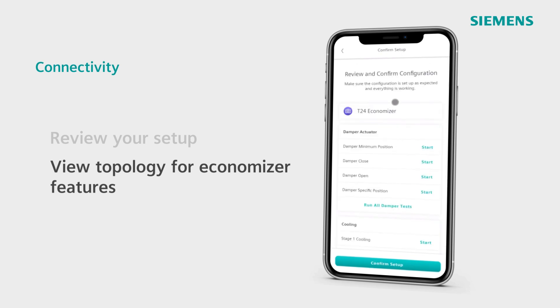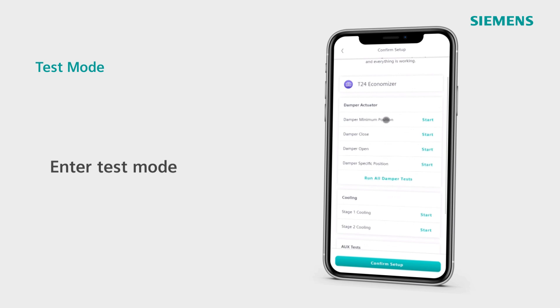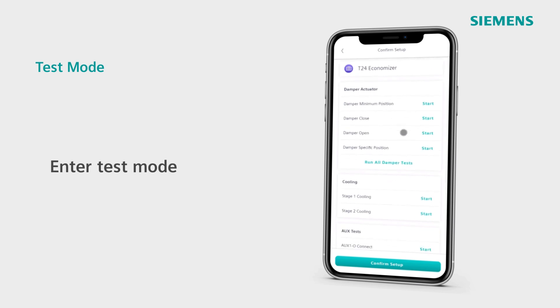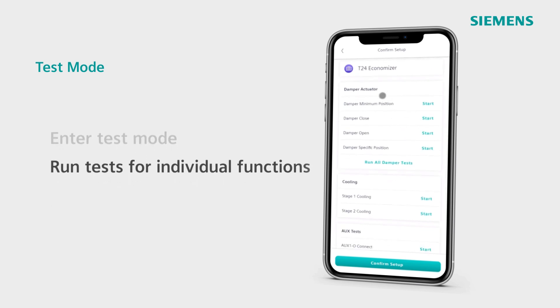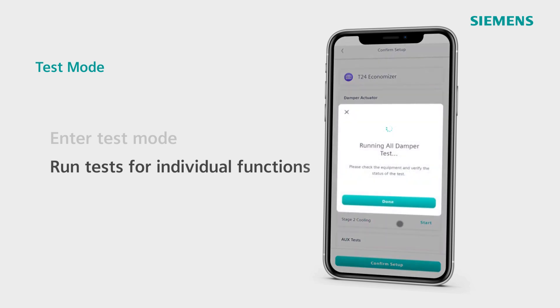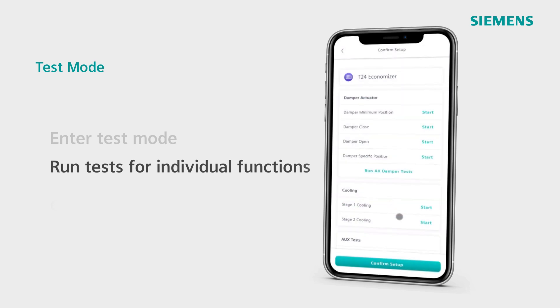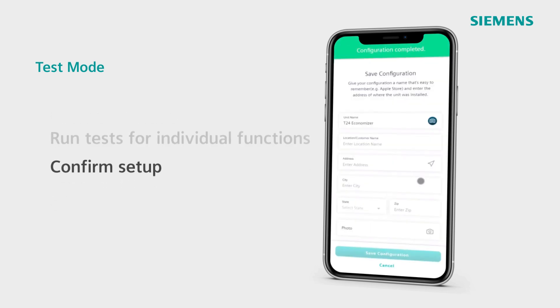Once you confirm your setup, users can enter a test mode to ensure that the Economizer is operating properly. You can test settings and stages for damper actuators, cooling stages, and auxiliary outputs as a group or test them individually. Confirm that everything is running properly, then confirm your setup.